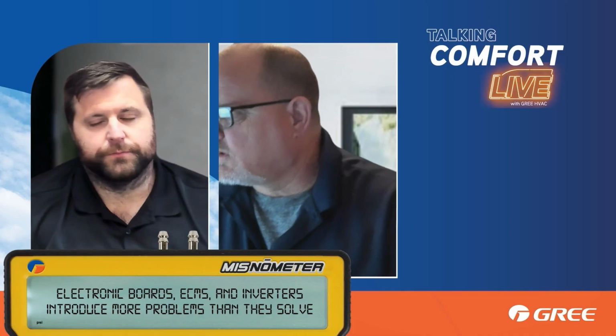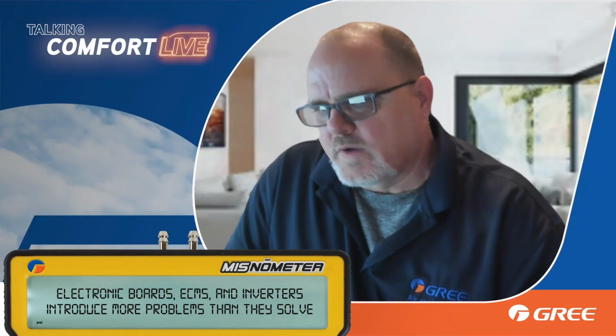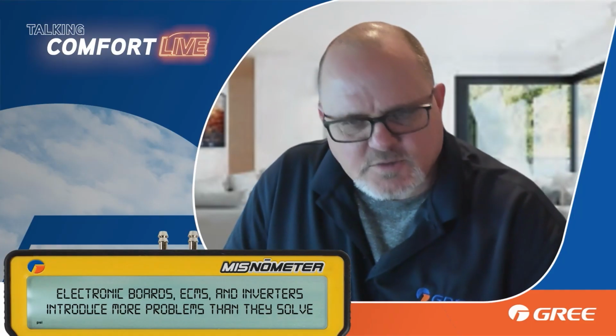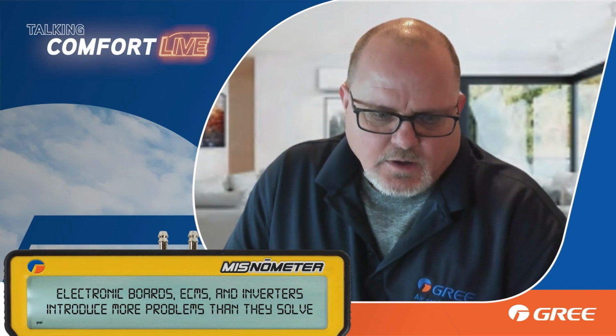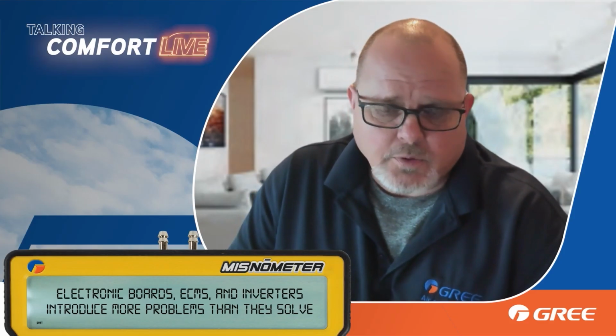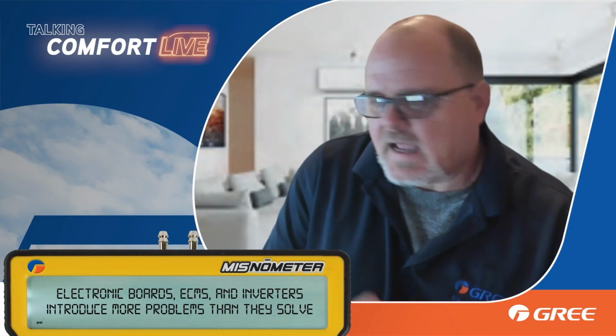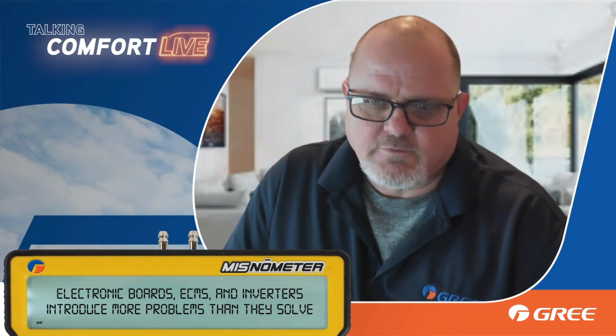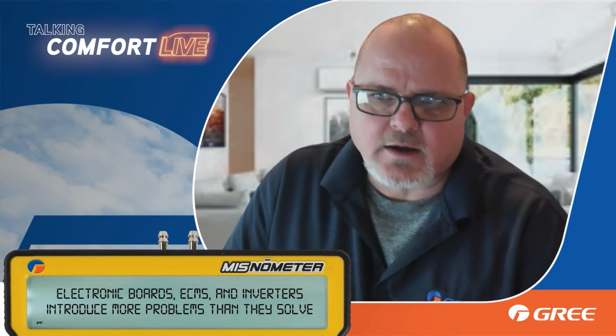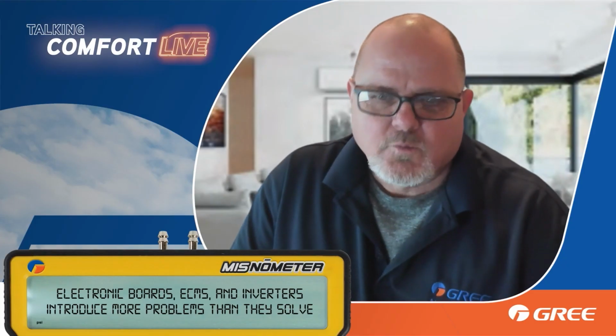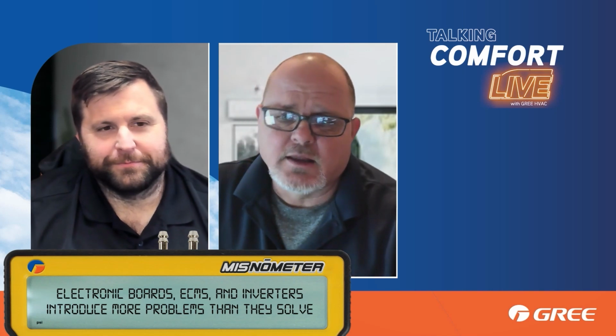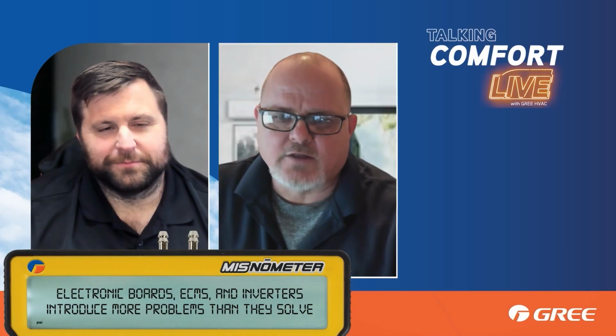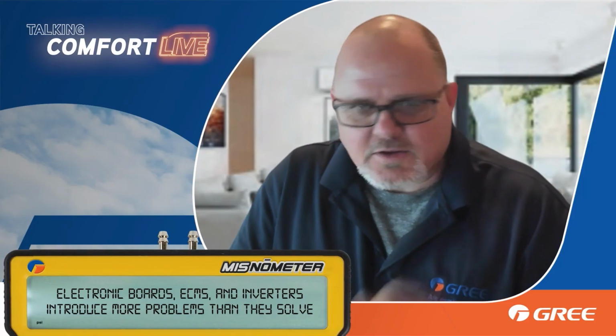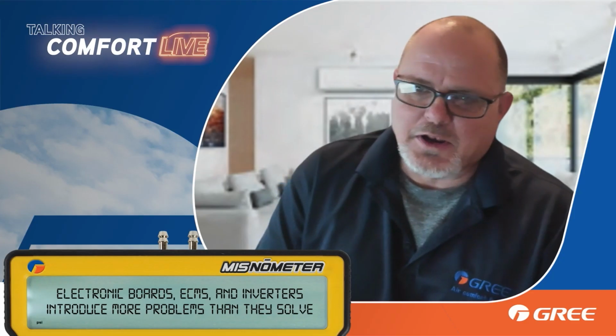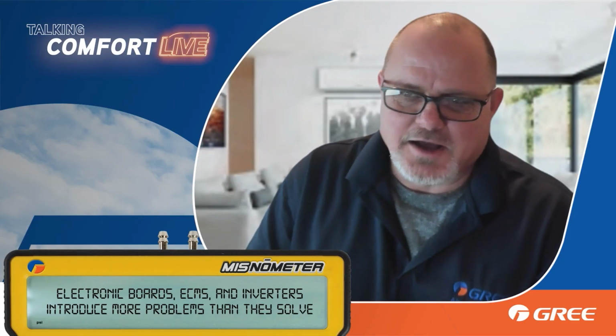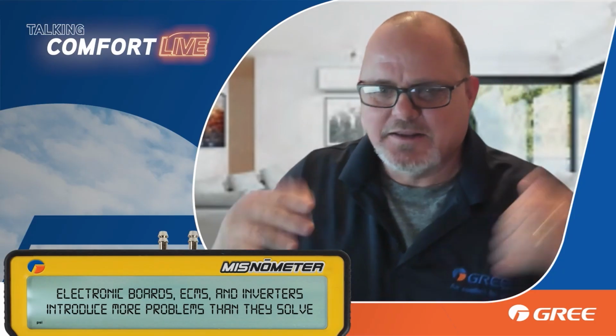Well, and I think, James, that if we were in a little bit different era right now, and we had the improvements in more and more mini splits being sold in this country, more and more of the multi-zone type units, whether it be a multi-zone mini split or even the multi-pro, let's say that all that got more popular before our government actually phased out incandescent bulbs. It would prove a point real quick. Yeah. And I'm sure everybody on this broadcast has probably at least worked on a heat pump or an air conditioner in the past, when they did have incandescent bulbs, and every time that condenser came on outside, the lights inside the house would dim, because we get this big, huge locked rotor amps to get that compressor started, and we put quite a load on that electric panel, which drops the voltage to all the light bulbs inside the house, and they all dim down for a second until the compressor is actually running. Then the light bulbs get bright again.